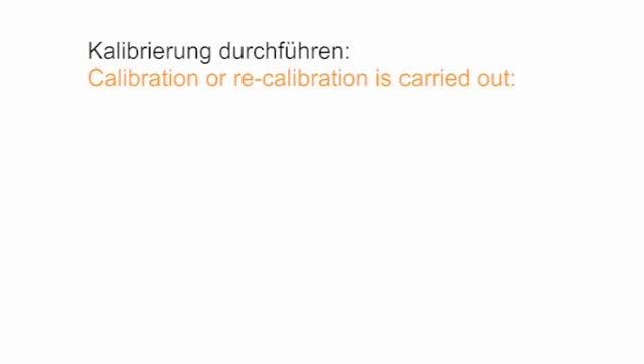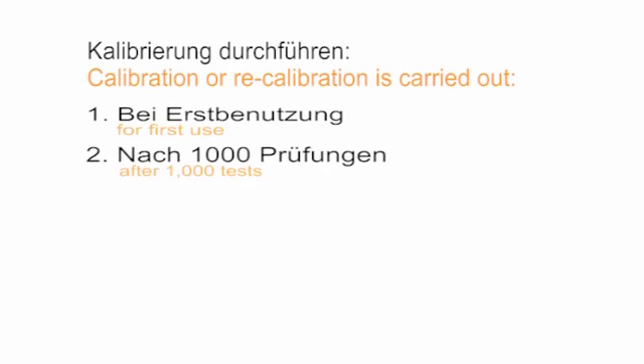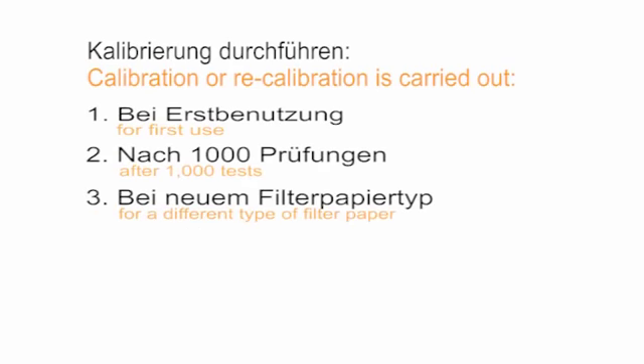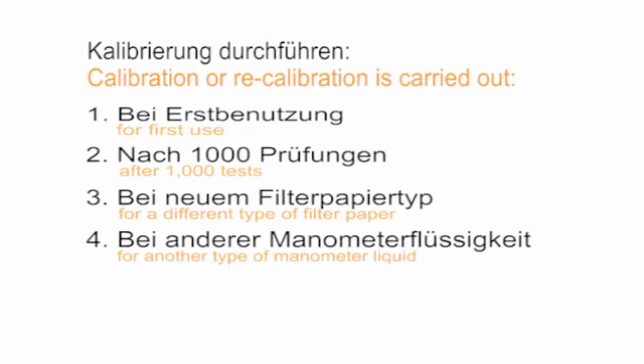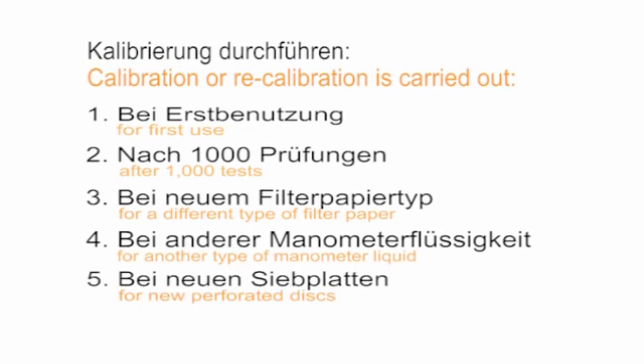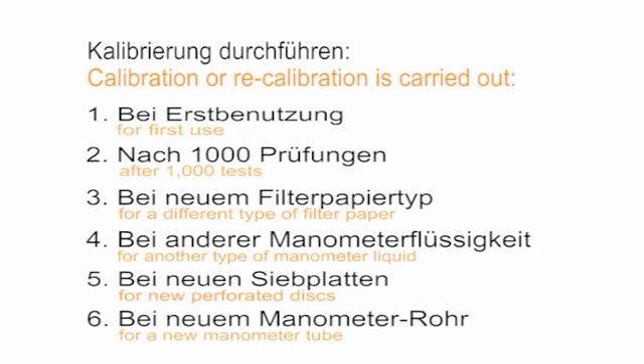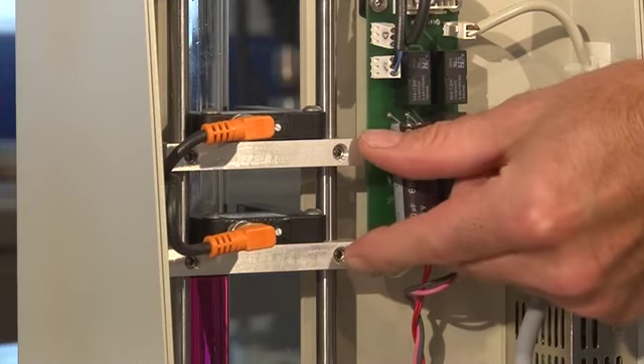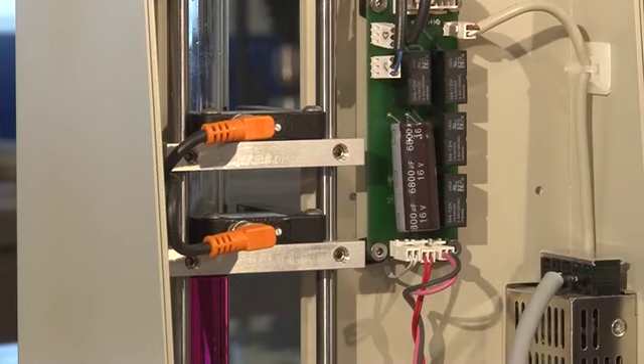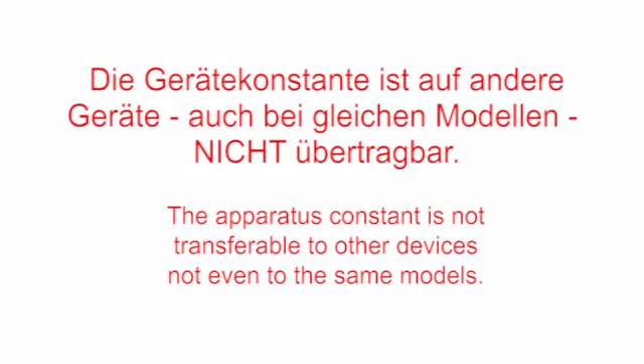Calibration or recalibration is carried out for first use, after 1,000 tests, for a different type of filter paper, for another type of manometer liquid, for new perforated discs, for a new manometer tube, and in case of systematic deviations of the secondary reference cement. If the measuring section on the device is changed, the apparatus constant must also be re-reckoned. The apparatus constant is not transferable to other devices, not even to the same models.